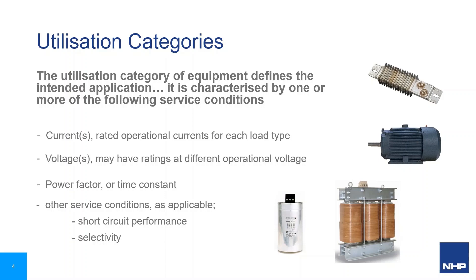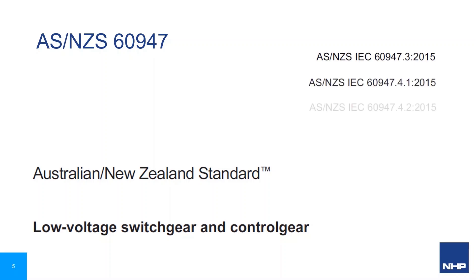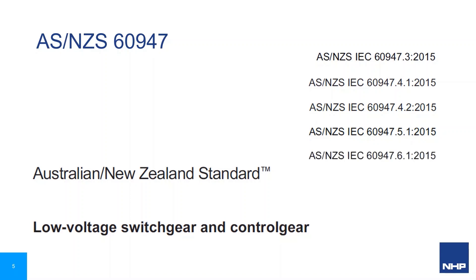Once we understand the utilisation, selection of a device can then proceed based on rated operational voltage, rated current or power of the load, and control functionality required. Utilisation categories are defined for specific equipment types, being disconnectors and load switches, motor starters, control circuit devices, and transfer switches.